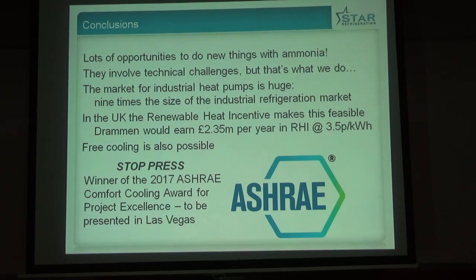If you were just to throw it at the building and not care about it, you would get into trouble, no doubt about it. But if the system's properly designed and properly maintained, and my argument in that sense would be, you have to properly maintain it, because you won't keep the energy efficiency and the reliability if you don't. And in this case, the business case is totally dependent on the efficiency and the reliability. You get better efficiency and reliability from ammonia, but you'll only keep that if you maintain it properly. So having skilled staff to maintain it shouldn't be seen as a dreadful disadvantage.